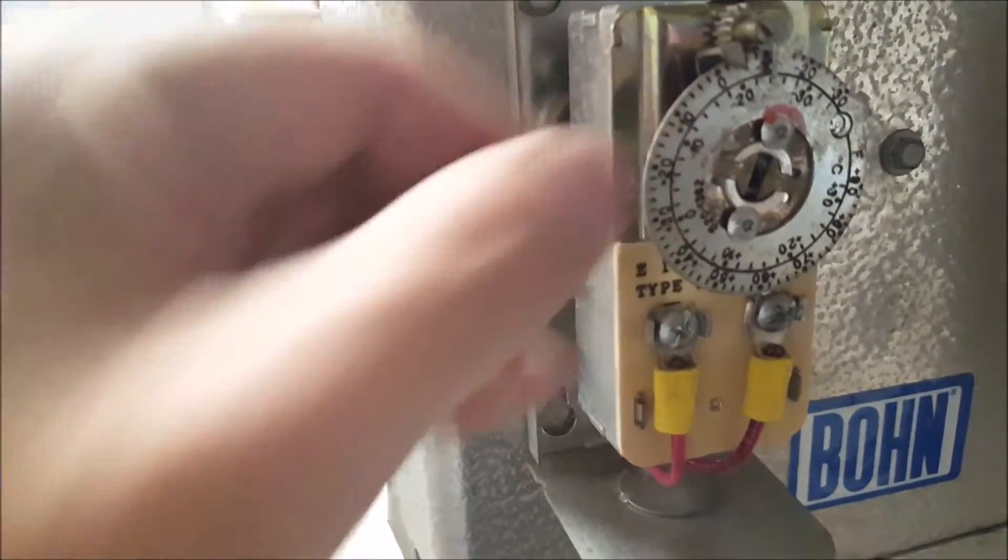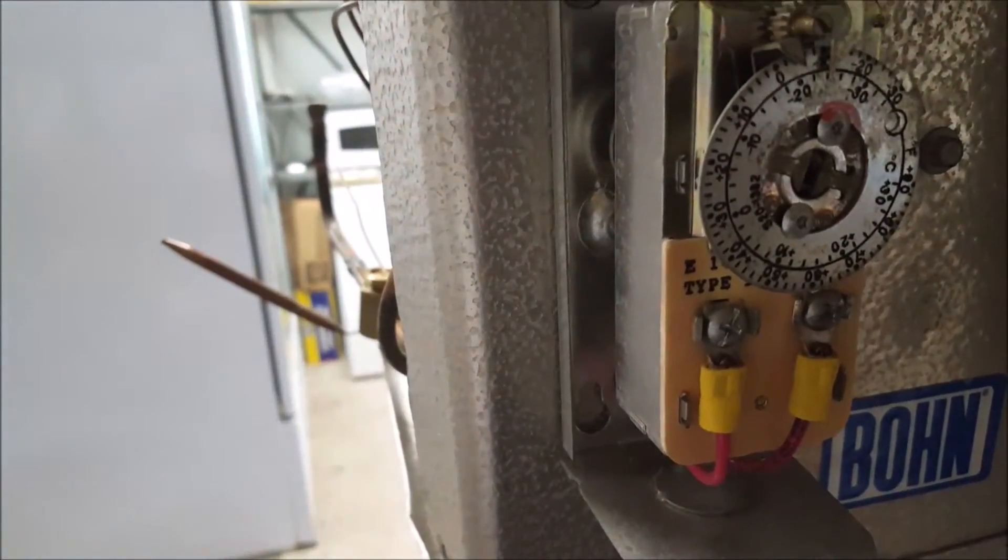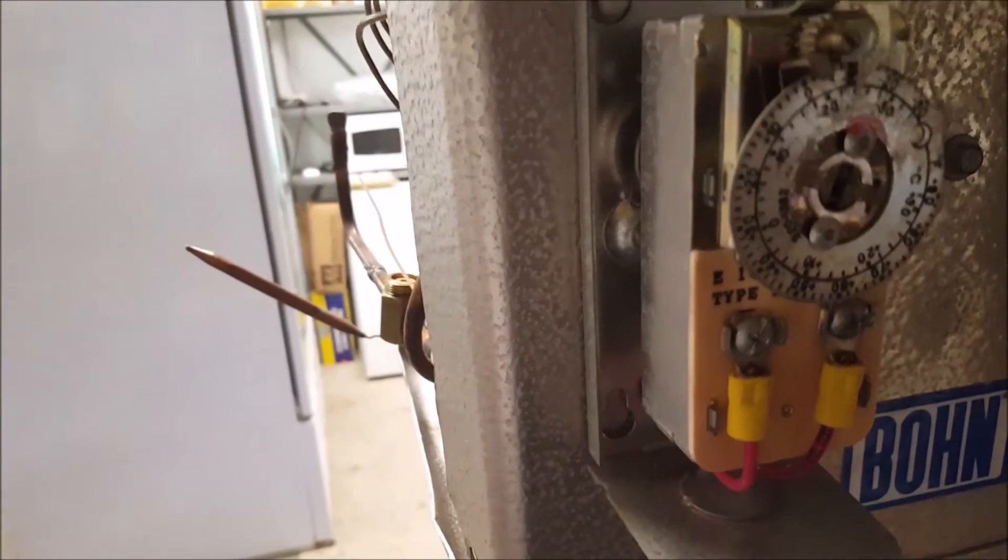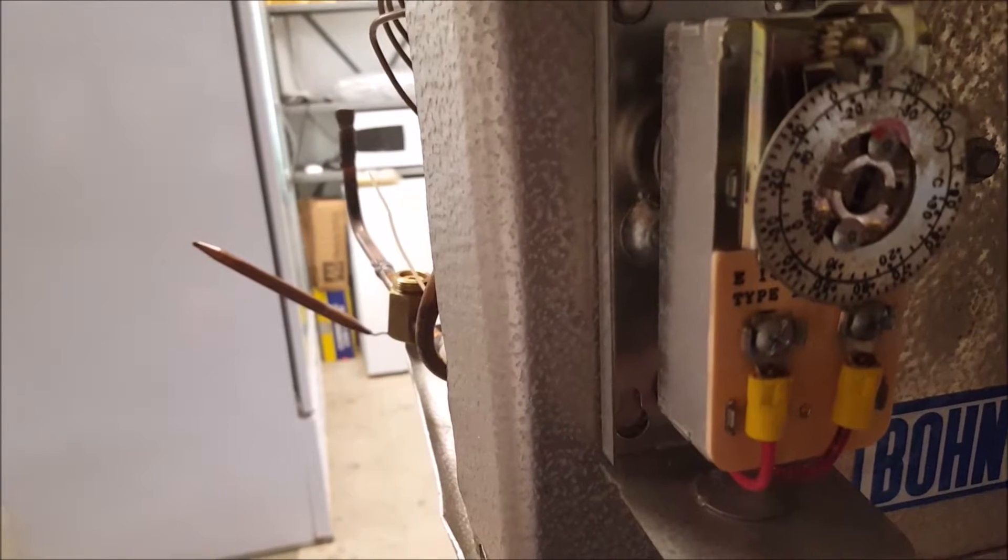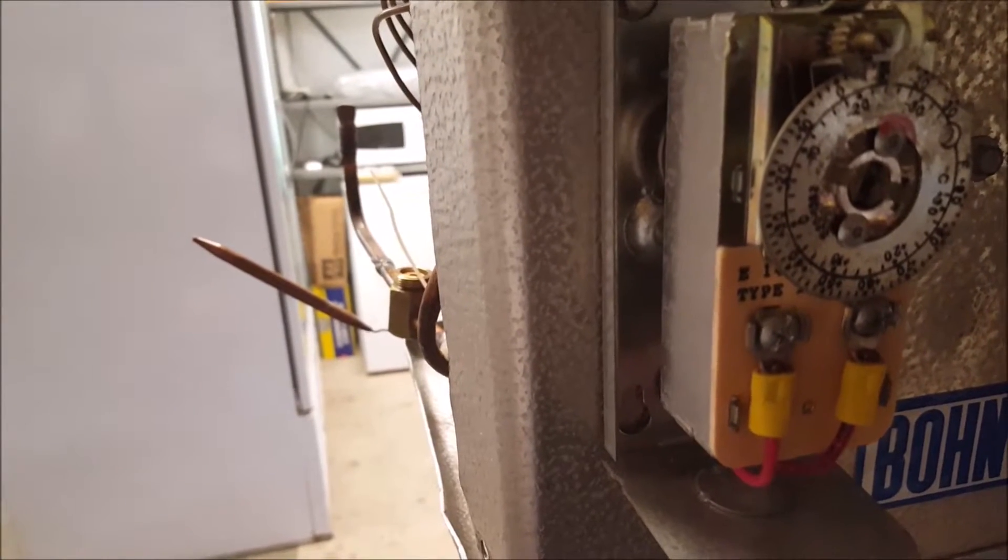If you notice this other little arrow next to it here, that's the temperature at which it's going to come back on. It's going to cycle back on. Generally there's about a six degree differential, so if it cuts off at negative 10, it will cycle back on somewhere around negative 4.